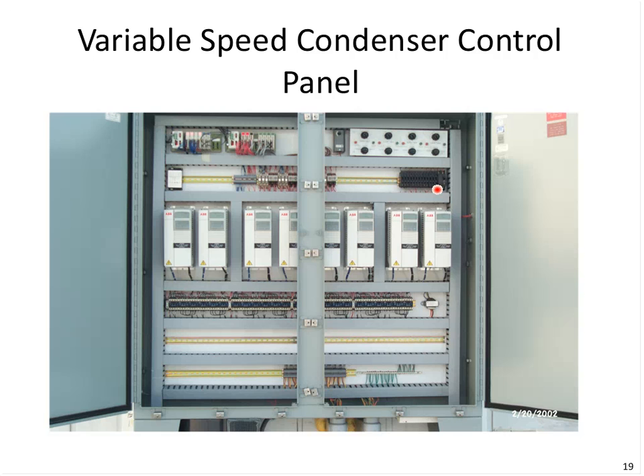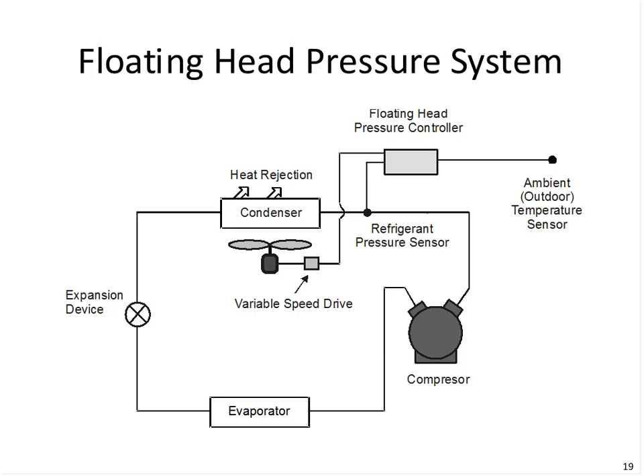Other reasons why floating head pressure is sometimes not pursued is flash gas. Sometimes as the liquid from the condenser is heading to the metering device, if we lower the pressure, little vapor bubbles form in the liquid line here, which results in erratic operation of the metering device. So that might be a concern. Liquid feed problems.